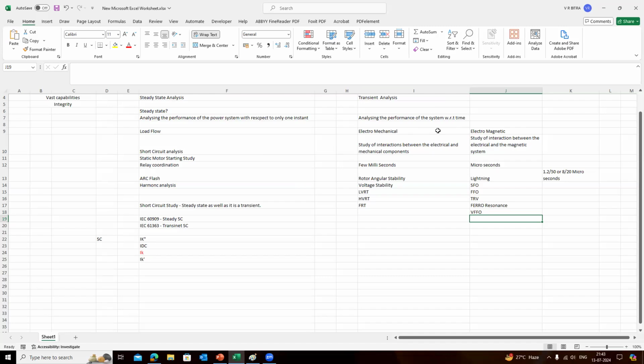And the RMS study is like angular stability, and probably if you want to do a study for grid islanding, finding out the critical fault clearing time, these all come under the classification of electromechanical transients. And studies like slow front overvoltage, which is logically the switching studies, fast front overvoltages, which are logically called the lightning studies, very fast front overvoltage, which is applicable only for GIS substations, and transient recovery voltage and ferroresonance. So these are all the studies which come under the category of the EMT.